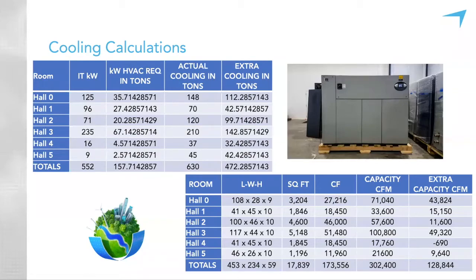We always plan for failure in data centers. We have redundancy, N+1, 2, 3, and 4, in almost every fashion you can imagine. With newer technologies, we can do what I call teaming the CRAC units, where we connect them through a standard network switch so they all talk together and work as one. Now we can look at N+1 a little differently. I cannot tell you what is right and what is best. Every data center has to make its own decision on this.